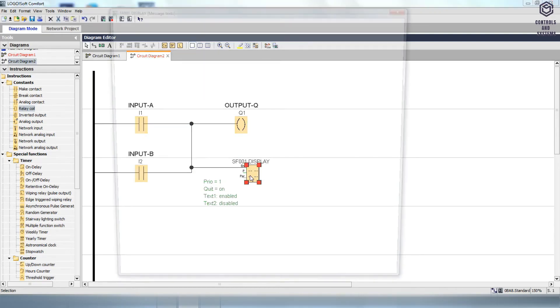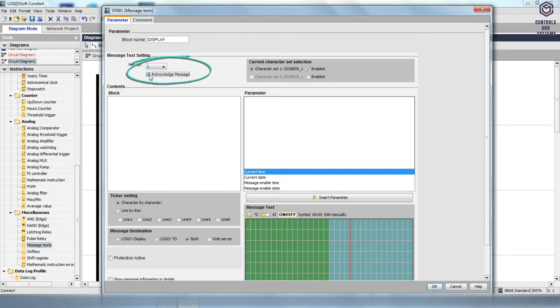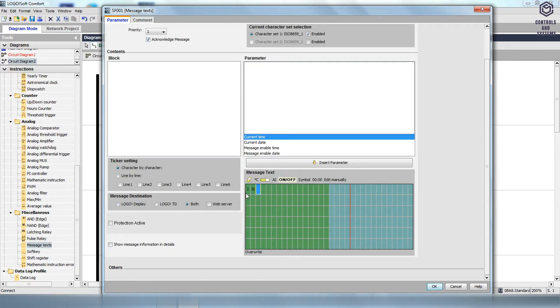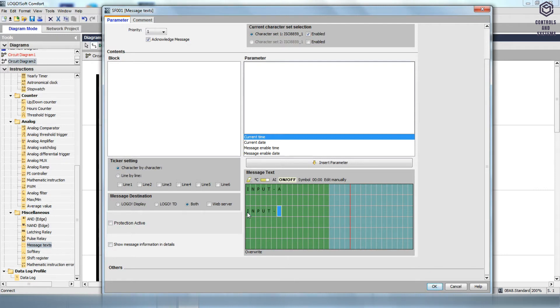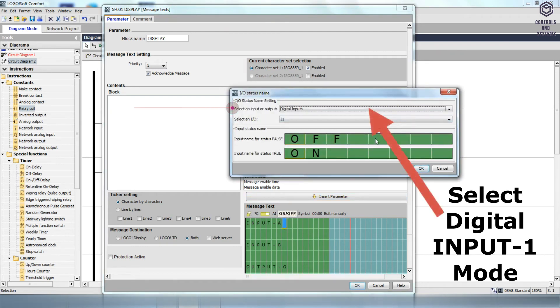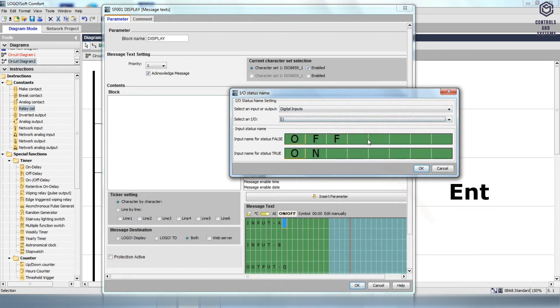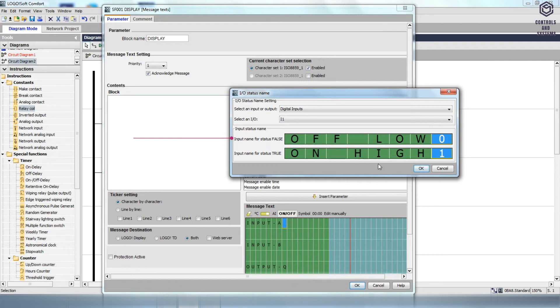Double-click the Message Text block and a dialog box will open. Enter any name in the block name box. Next, select the priority value and enable the Acknowledge Message in the Message Text setting. Go to the Message Text and enter the input and output names on the green text screen. Enter the names like Input A, Input B, and Output Q. For Input A, click the ON/OFF option and the I/O Status Name dialog box will open. Select the Digital Inputs, then select I1 from the Select an I/O box. The input name for status false is 0 and low, and the input name for status true is 1 and high.